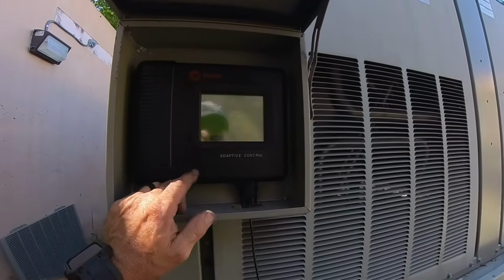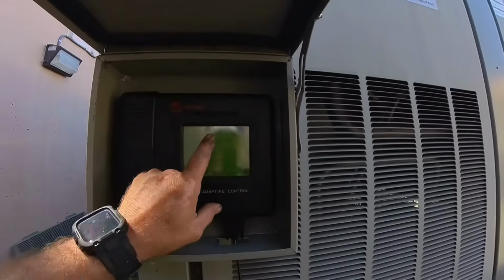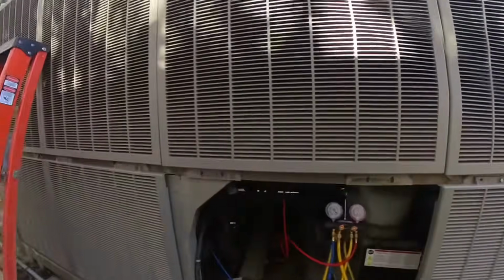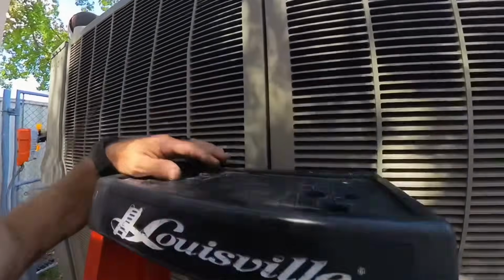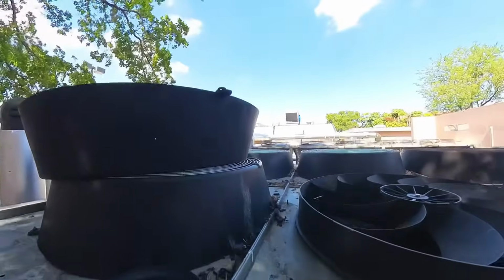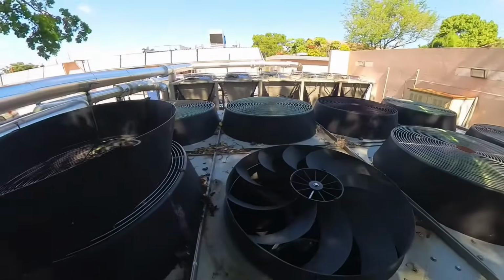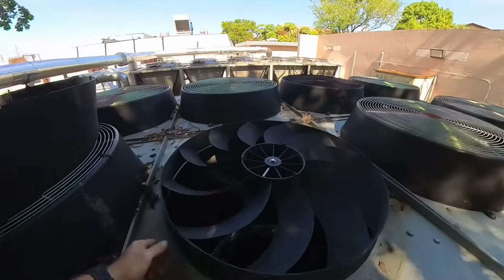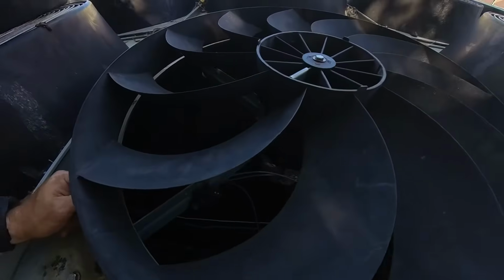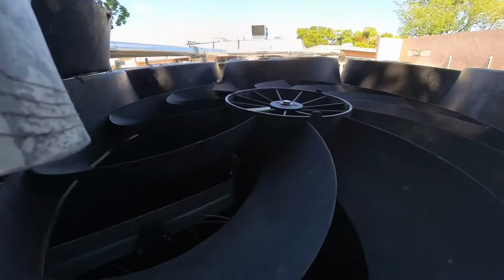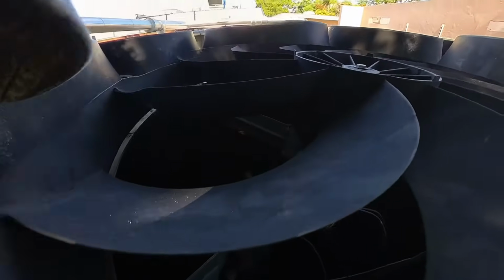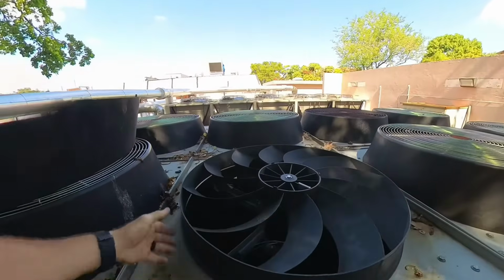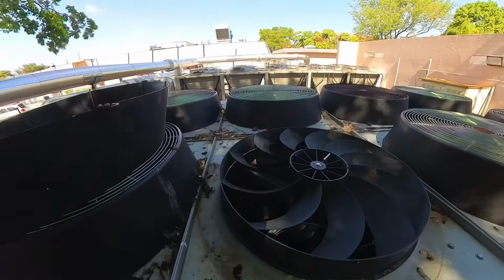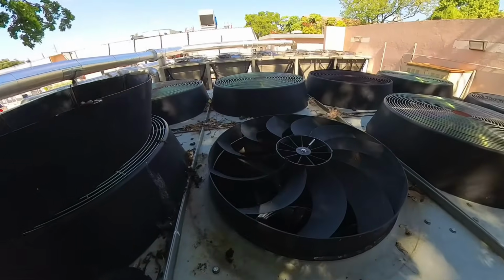Alright, things were working okay until we started getting loaded up, and my discharge pressure has shot up to 432. Still reading low, but I went up top here to check the fan motors. I got 3 out of 4 running here. This one, it's not even plugged in. So, I don't know what the heck happened here. I see some broken pieces down in there, but this is also rubbing. I'm gonna have to shut her down again and find out why.